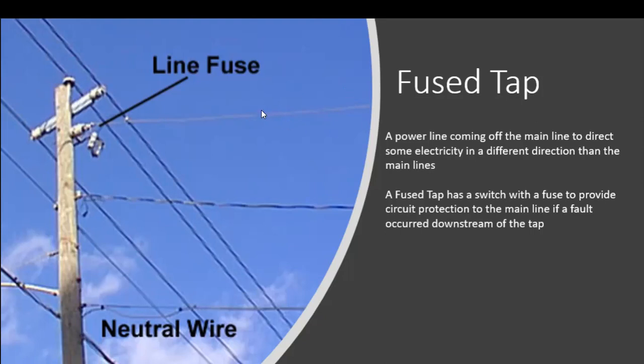Now the problem with that is if I have any kind of problem here on my tap line, a tree falls on it, it falls to the ground, not only is it going to be a problem with the tap line, but it's also going to take out the entire feeder because the breaker will open at the substation. I don't have any fuse protection on a solid tap line.